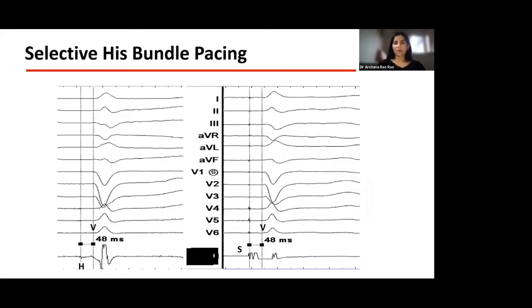Having identified the His bundle, all you do is deploy the helix of the lead itself, the Select Secure, and you do that by a clockwise turn on the Select Secure lead, so as to get the helix embedded in the His bundle itself. In doing so, you can often spot an injury current, as you would with most active leads. And what you tend to do is measure the HV interval and the interval between the His spike and the end of the QRS complex.